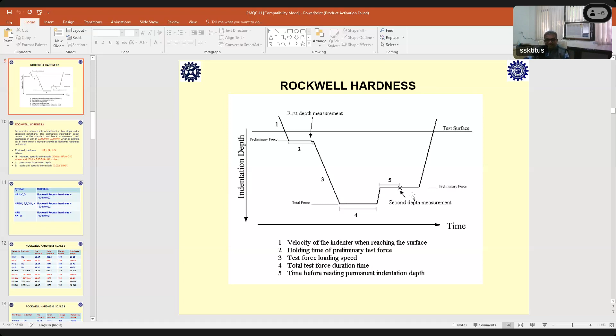Okay. Now I think this is what I have already explained to you. After making the permanent indentation, you measure the indentation depth in mm. So I told you, if you get a 100 micron depth, then this is h by n. h is the depth, and you divide it by 0.002 mm; you have to convert that, in mm or micron, whichever way you feel is convenient. And then you will get a number, say 50. I am giving an example of 100 micron, so 50.